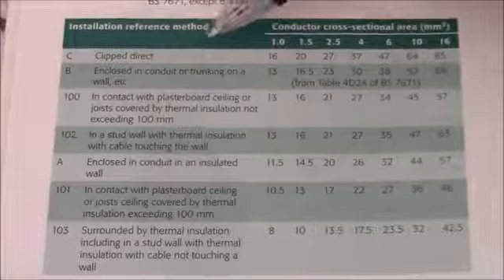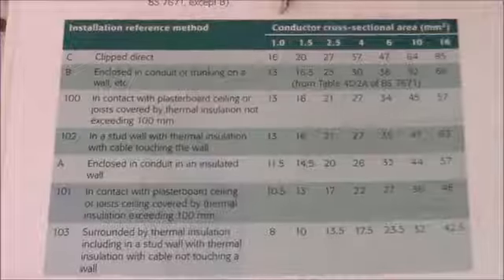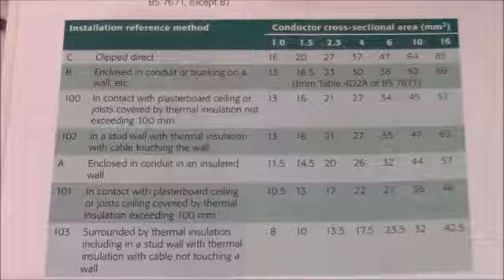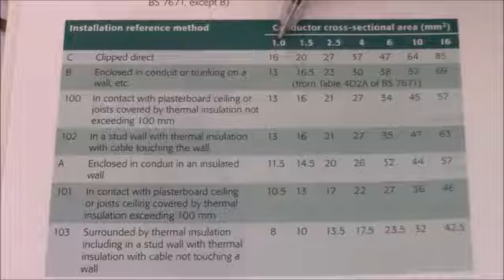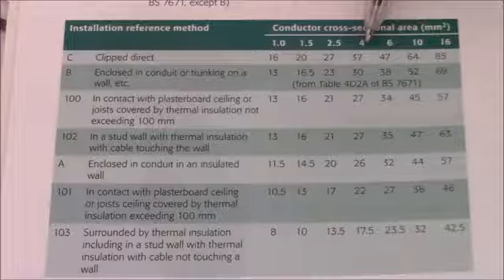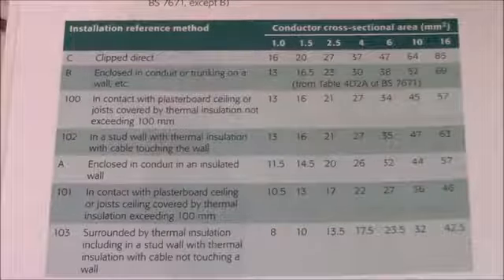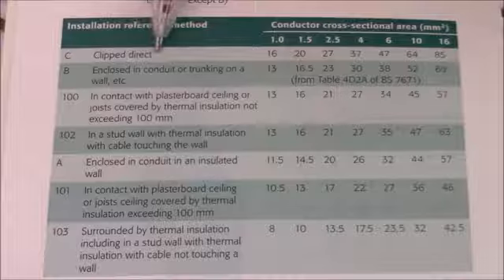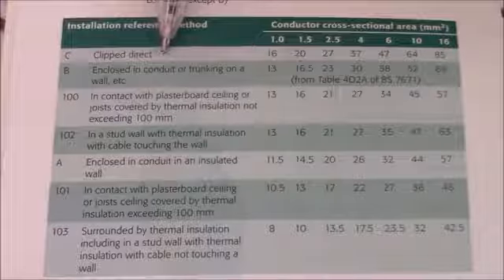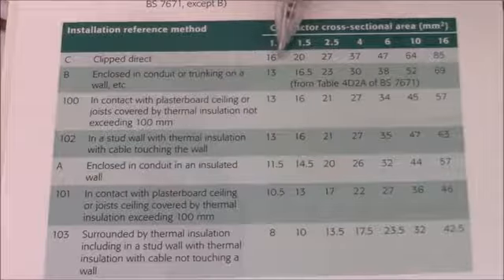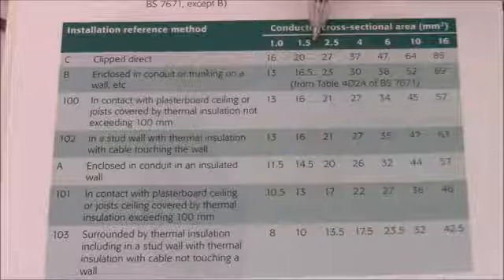It depends, obviously, on the method of installation. On this side, where the numbers are, you've got the conductor cross-sectional area, basically the sizes of the cables: 1.0, 1.5, 2.5, 4, 6, 10 and 16. Now on this side there's the installation reference method. Clip direct is basically when you clip the cable directly to the wall, and this is the rating for, let's say, 1 millimeter cable, 16 amp, 1.5, 20 amp, 2.5, 27 amp, and so on.